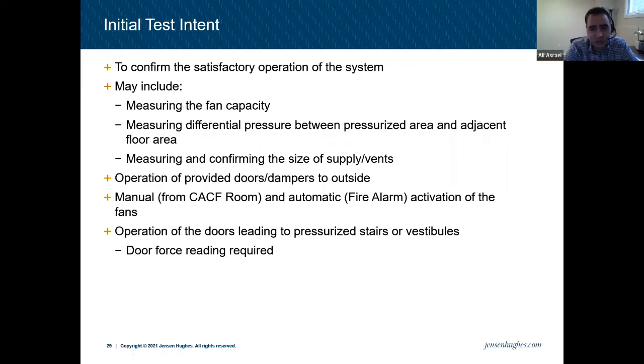It's 90 Newton permitted as a maximum in the OBC. But we have to talk about it in SB4. There is kind of a permission. It basically tells you you can't design a pressurized area with a door force reading less than 130. That would be challenging. So 130 Newton is sometimes what we consider, which is interesting because the building code is asking for 90, but when you go to SB4, it says it's basically impossible to design a pressurized area with a door force reading of less than 130 Newton with the measures that are in the OBC and SB4.